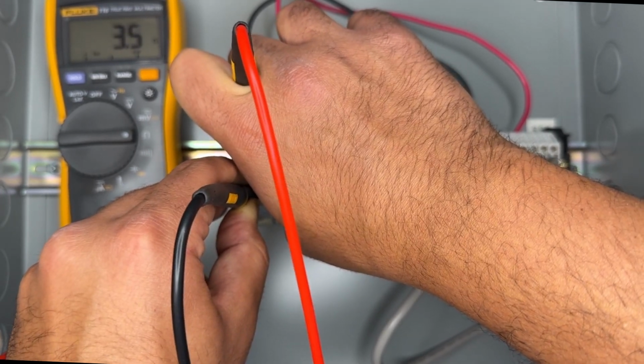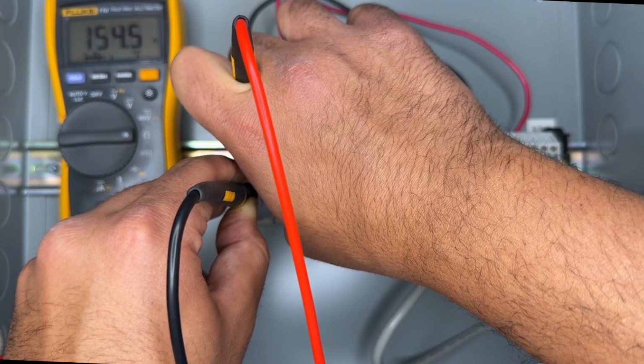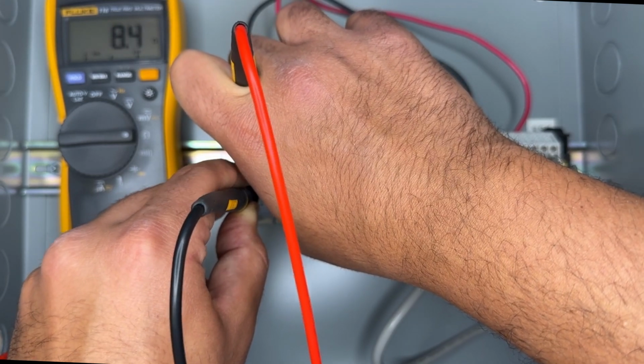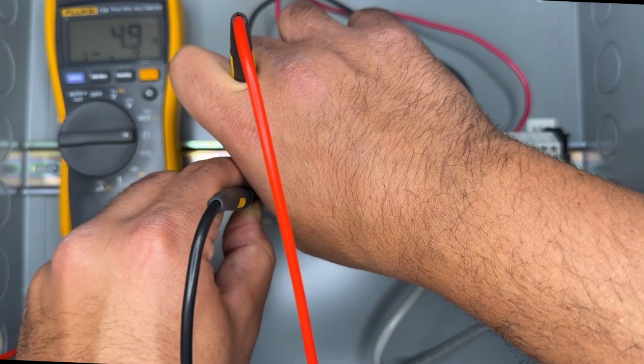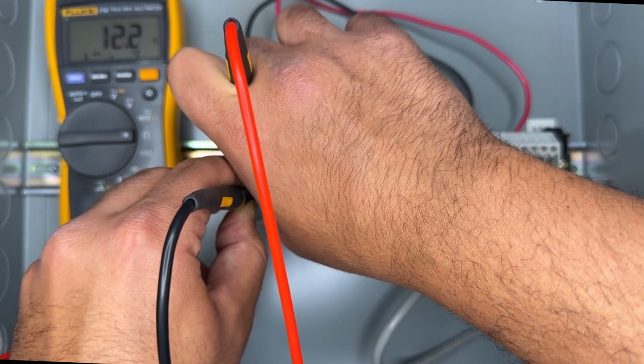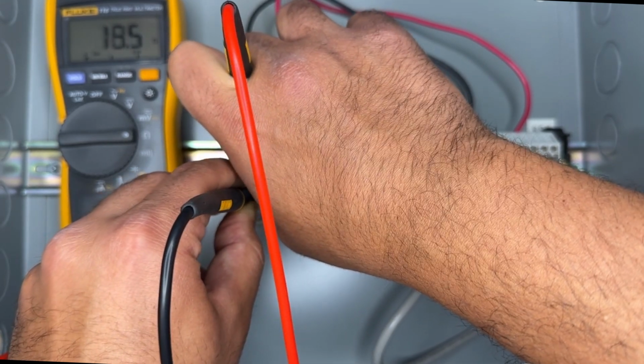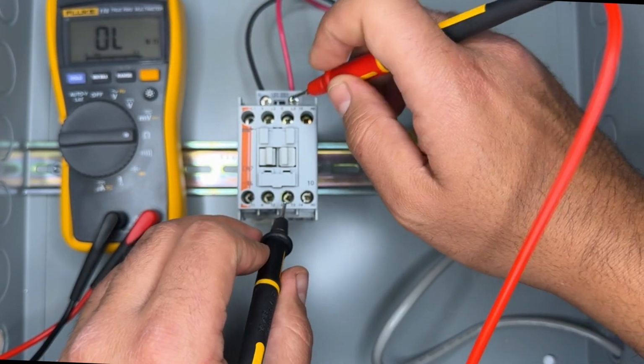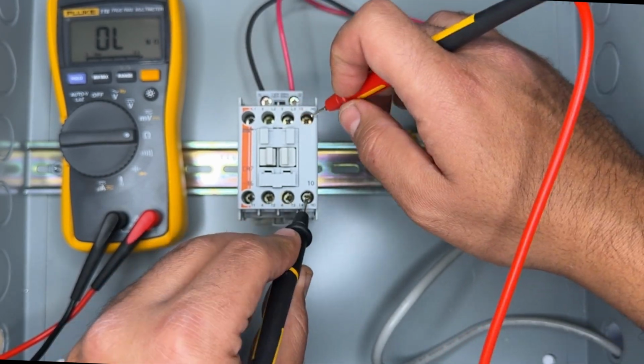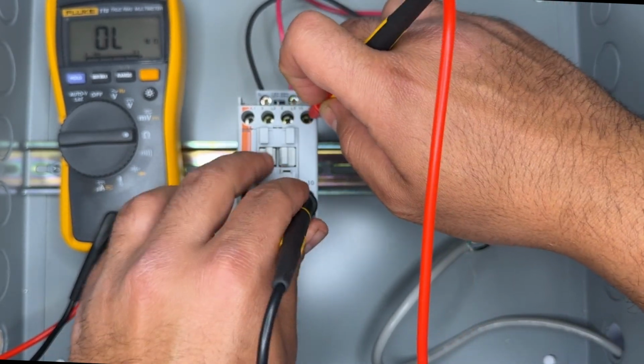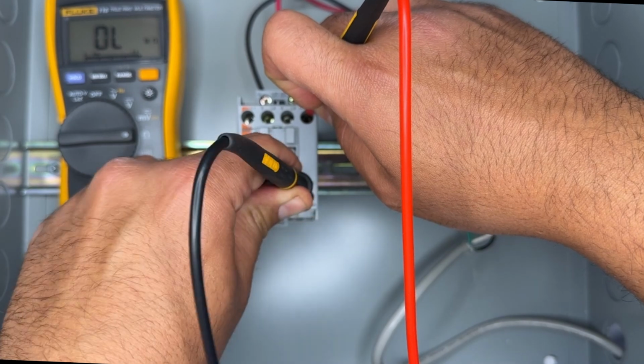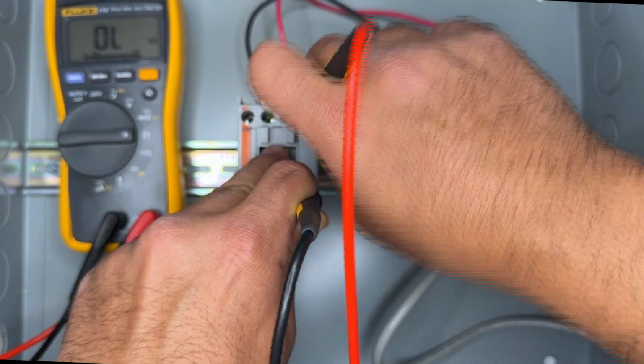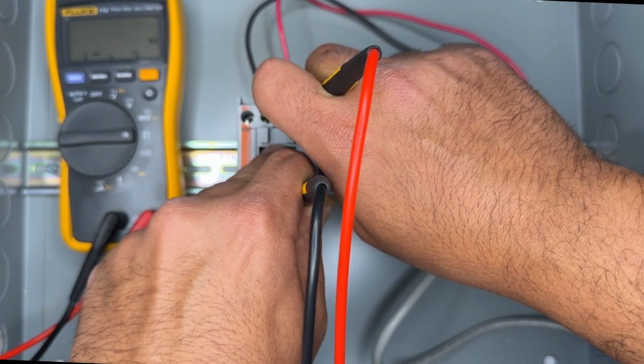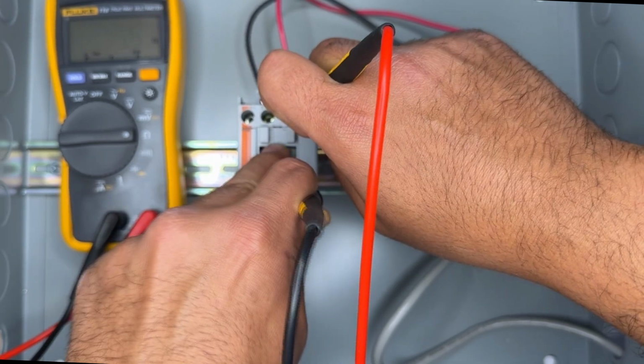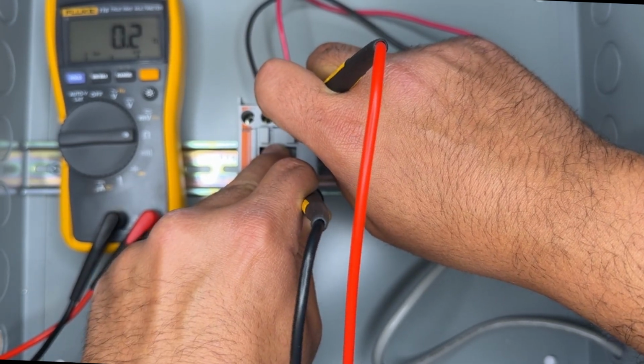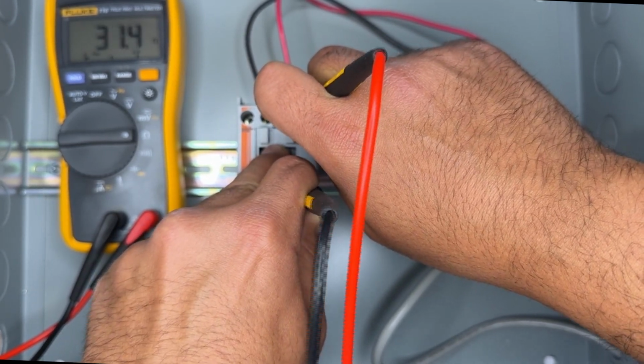So we've got about 3 ohms there. So what we want to see is as close to 0 as possible. It's jumping around a little bit there just because my hands aren't steady. There we go, about a couple of ohms there. That's exactly what we want to see. So you're going to want to check across each of those contacts, as well as our auxiliary contact. Let's check that one as well. And we've got less than 1 ohm there, so that's good.